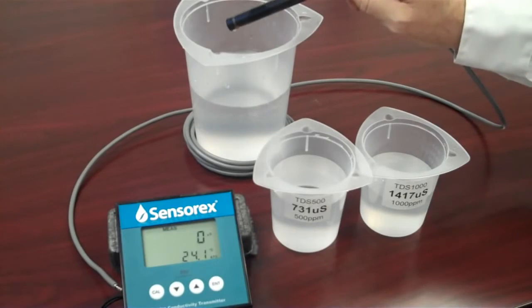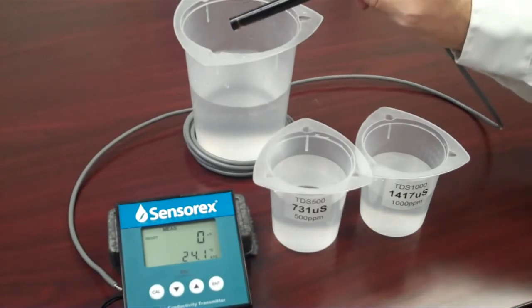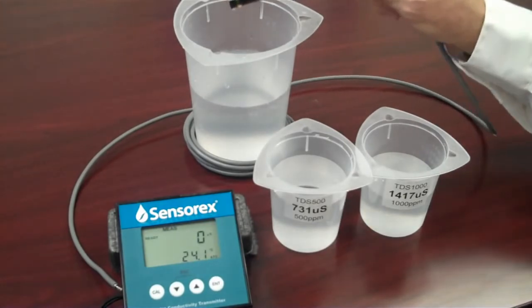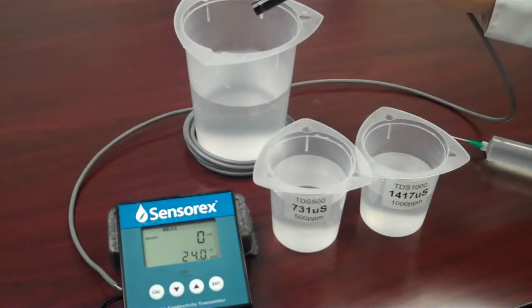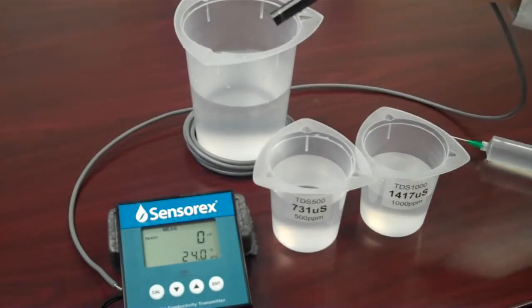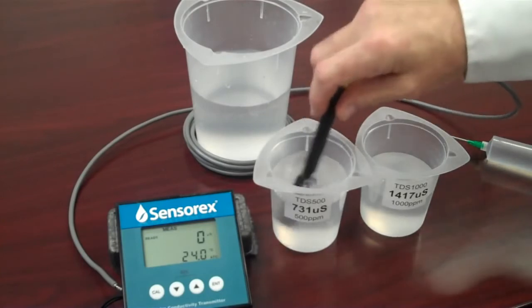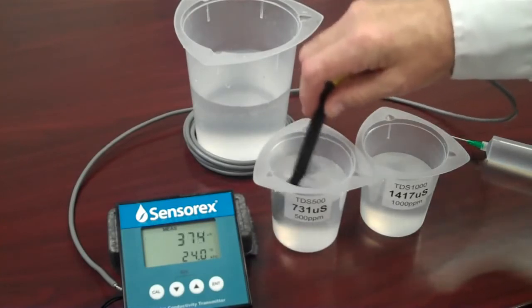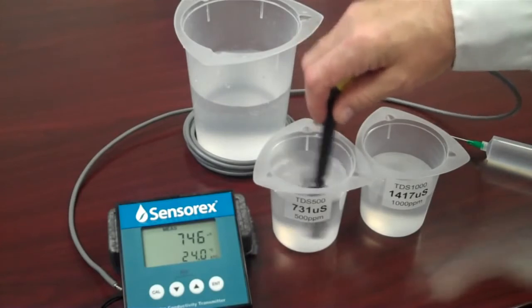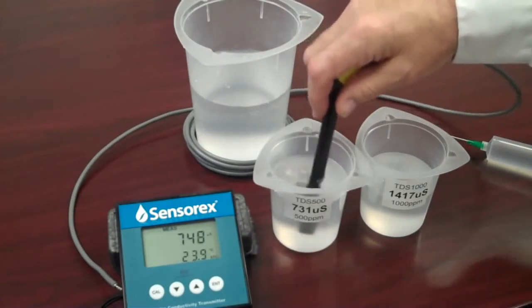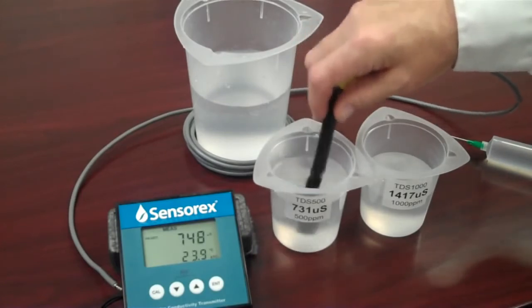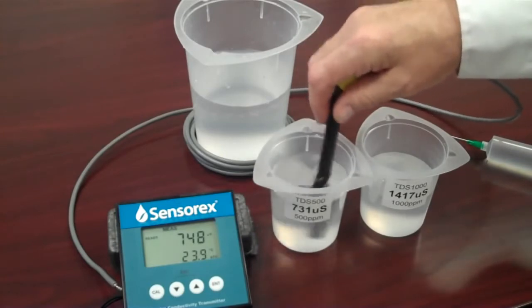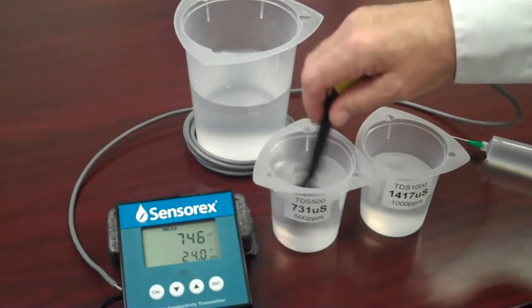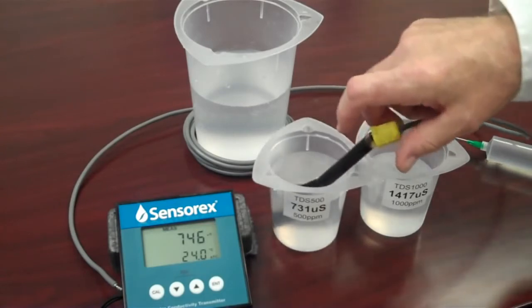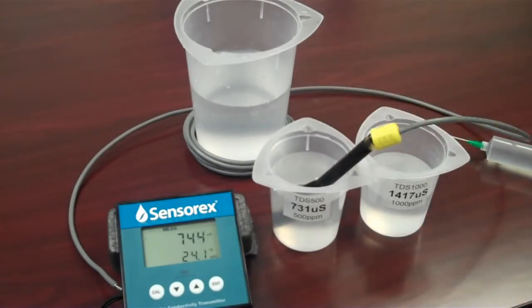Remove the sensor from the rinse water and rinse it with a small amount of the conductivity standard for best results. Place the sensor into a beaker of the conductivity standard solution. Today I'll be using a solution of 731 microsiemens. This is a mixed salt solution and it has 500 parts per million total dissolved solids. I'm swirling the sensor around in the beaker to remove entrained air bubbles and ensure a proper and stable reading. We have to wait a minute or two for the reading to stabilize.